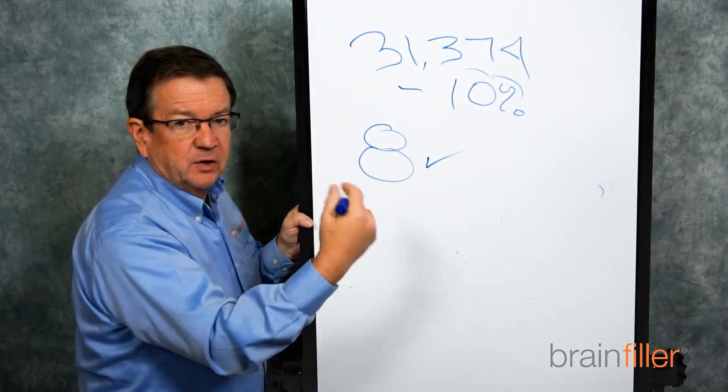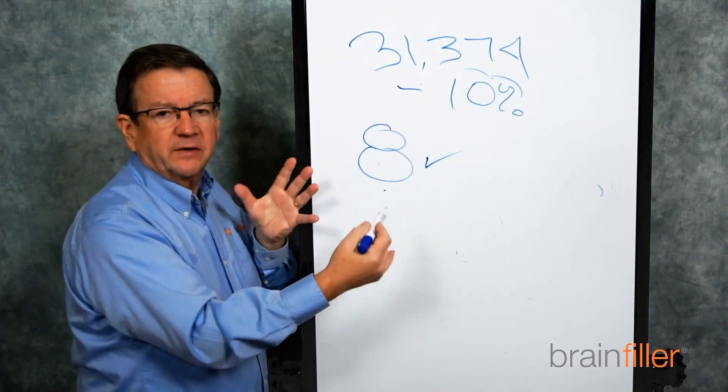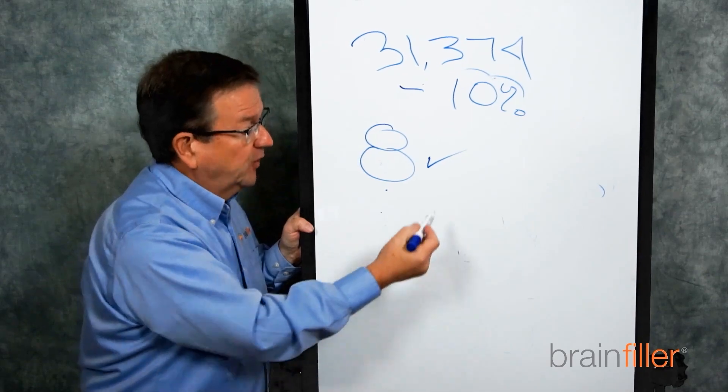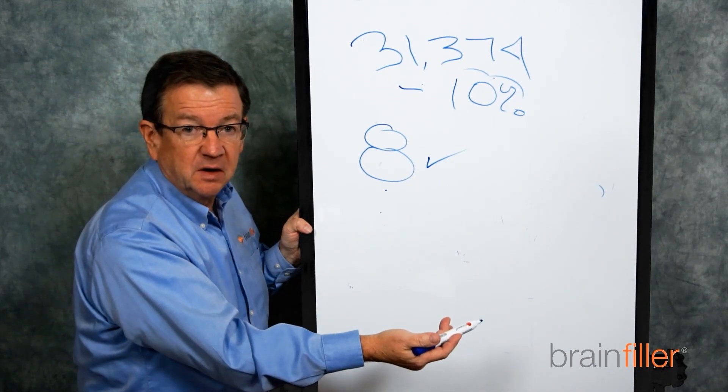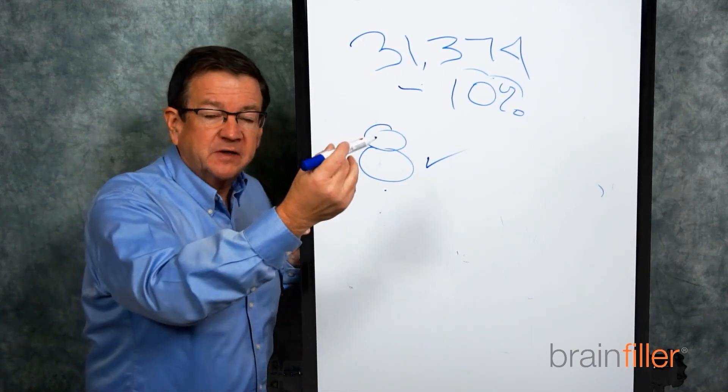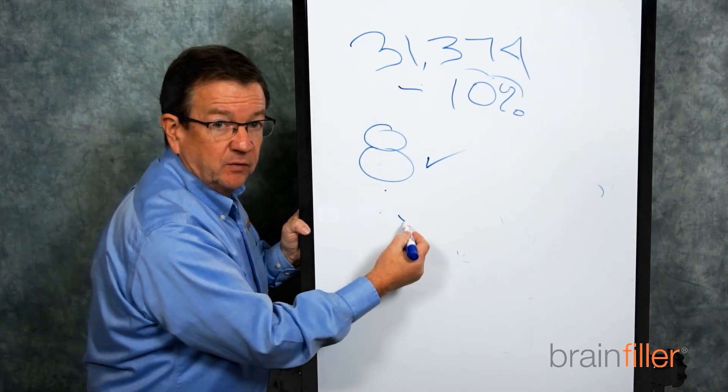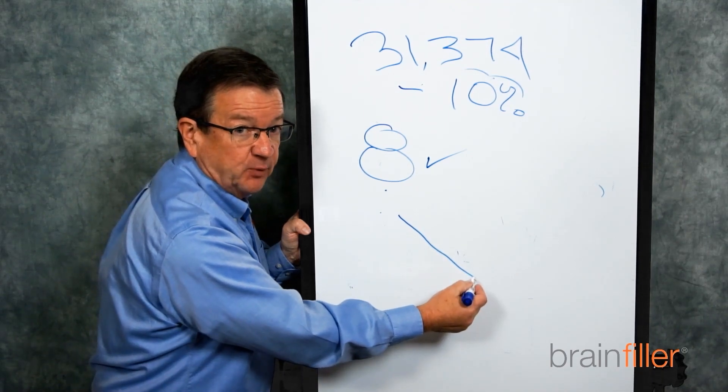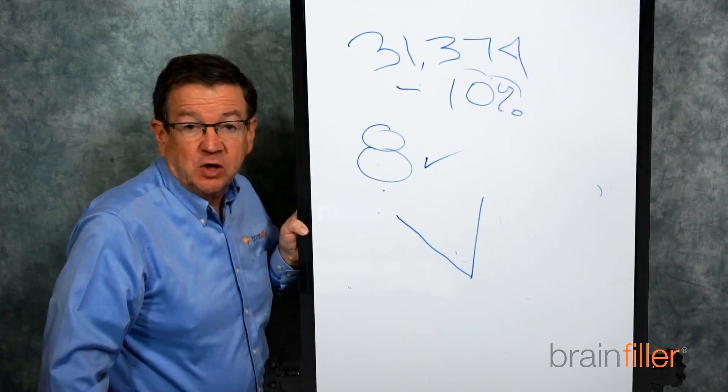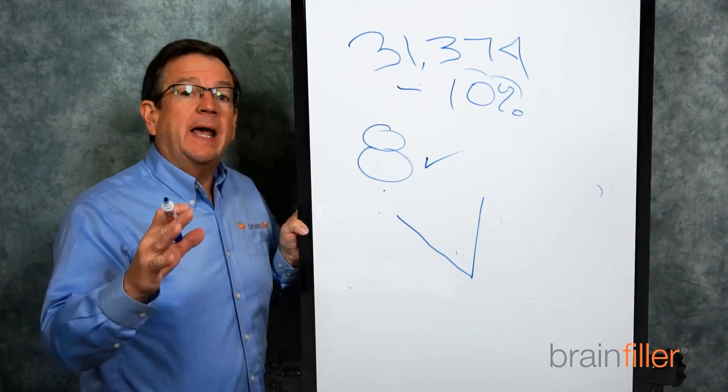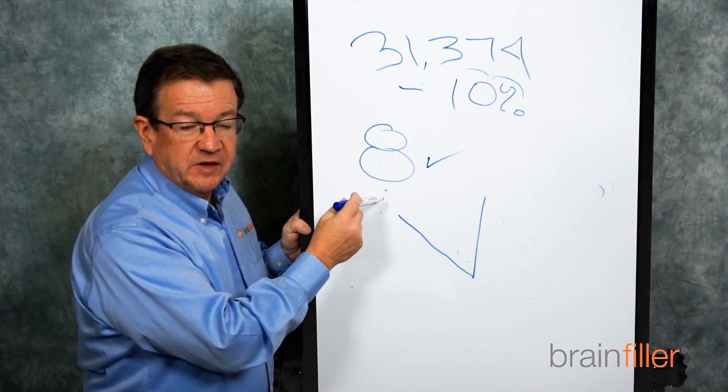Change it, then rerun the study, and go back and look at where are all the cases where 8 calorie, or whatever you select, the arc rating, where's it going to be sufficient? Hopefully, you will see all the same locations as being sufficient. Drop it another 10% and repeat the process. At some point, you'll lower the short circuit current to a value where instead of the incident energies coming down as you keep reducing the short circuit current, you'll find a value where all of a sudden it spikes. The incident energy goes up.